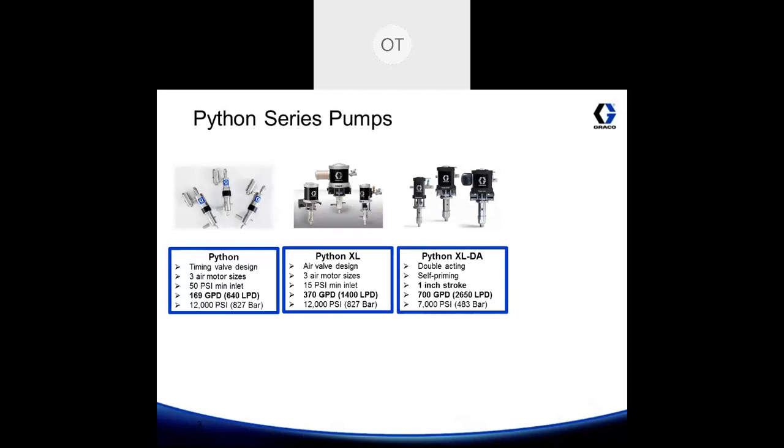The Python XL DA utilizes the same Merkur air motor for regulating air, except it uses a double acting pump, which doubles the flow when compared to a single acting pump of its class. It's also self-priming, so in the event that you need to prime your pump, you don't need to physically be there at the pump, and if you get any air trapped in your pump lower, it'll automatically purge itself of any air. These pumps come with a one inch pump stroke and can achieve a maximum flow rate of 700 gallons per day with a max operating pressure of 7,000 psi.